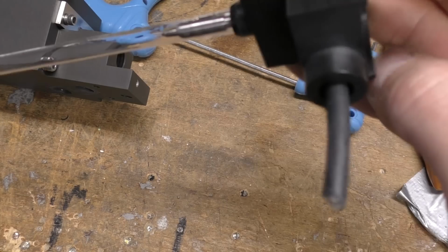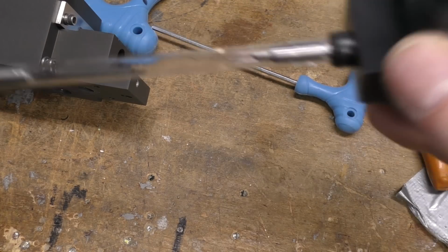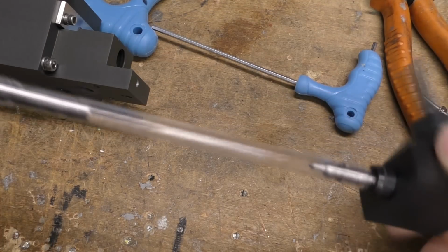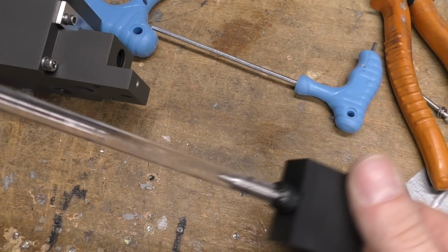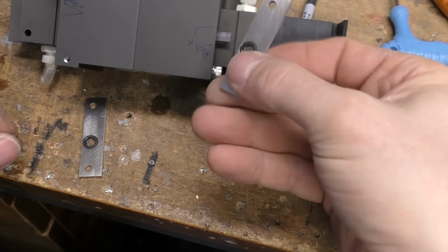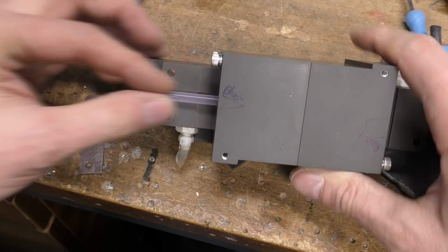So this is the actual main discharge tube. I don't know, high pressure xenon or something, may well be tuned to produce the maximum amount of the wavelength that the laser rod wants to absorb. And the laser rod's just held in by these 2 end plates with a couple of O-rings. Once those are removed, we can just take it off. So this is the actual laser rod.